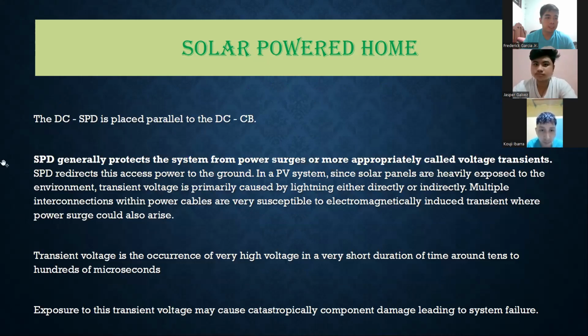Now, here we have the DC SPD, which is placed in parallel with the DC circuit breaker. SPD generally protects the system from power surges, or more appropriately called voltage transients. SPD redirects this excess power to the ground.